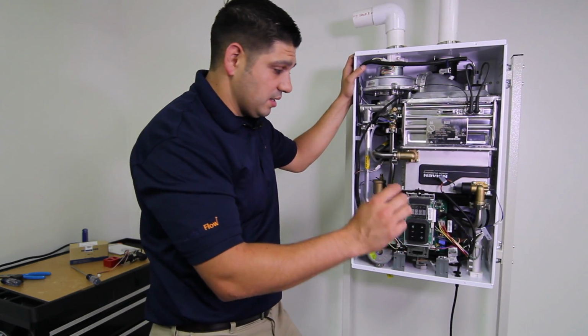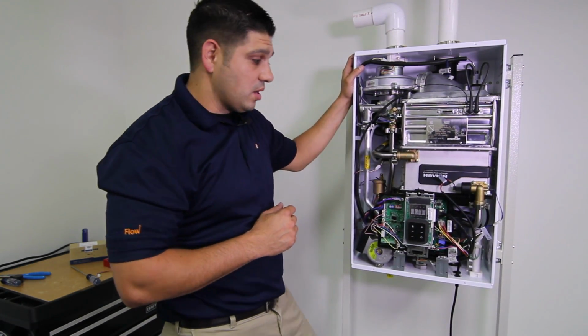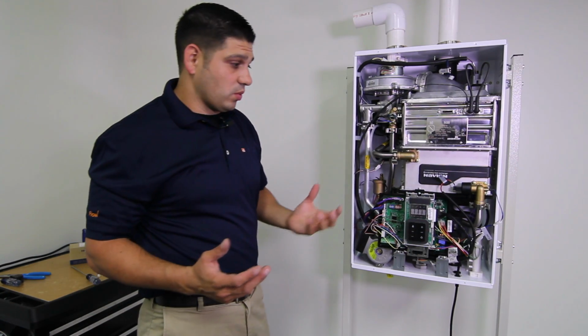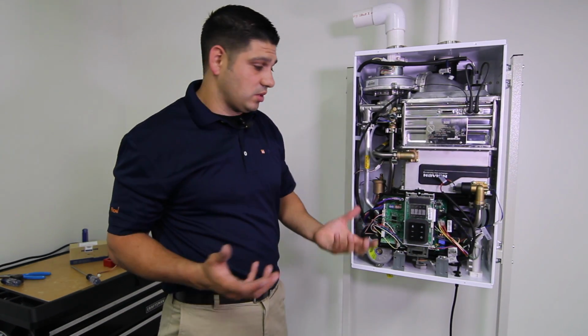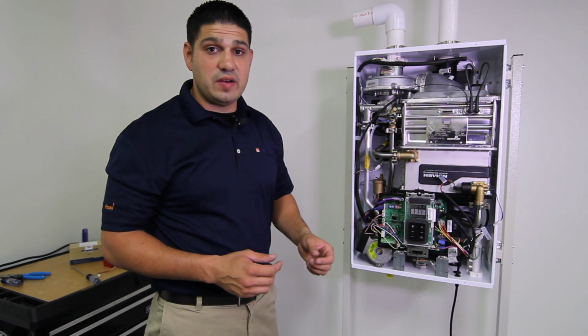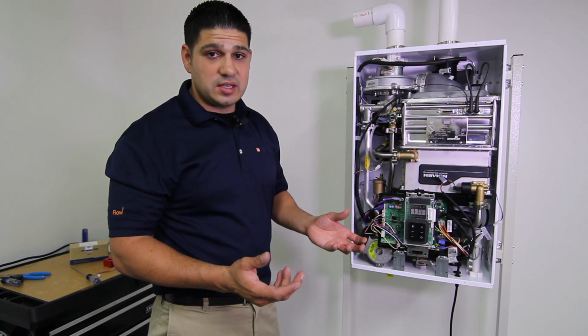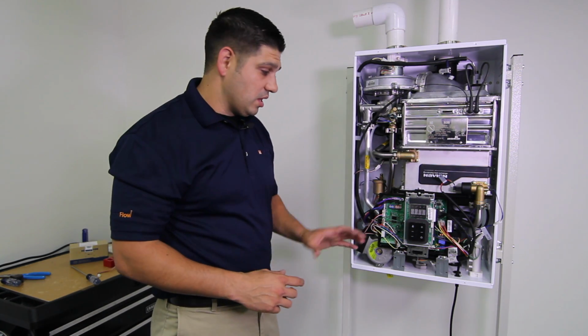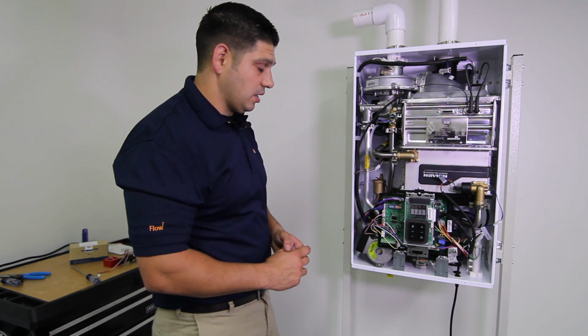Before we plug anything in, we're going to pressurize the system again to make sure we have no leaks. We'll allow it to go up to city pressure and monitor it. If you have any problems, you'll have to repeat the process and check the O-rings and what you have, but we really shouldn't have any problems.